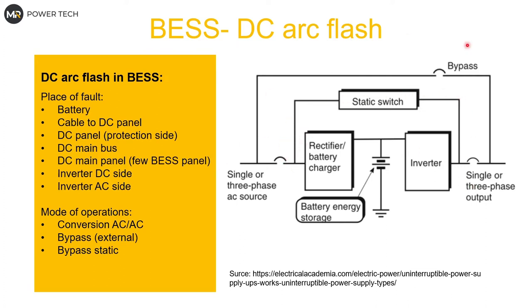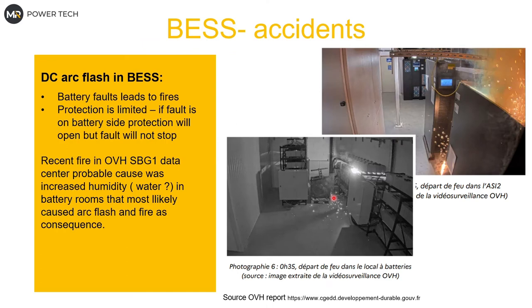Different modes of operation — bypass, double conversion, AC-to-AC — matter more for the AC side than DC. From what I found for real incidents: there was an accident at the OVH data center in Strasbourg, I believe in 2021. The official report — in French — stated it was a battery fault leading to fire, caused by increased humidity detected by sensors. For me, it looks like the battery fault created an arc flash which then caused the fire, and we know many websites went down because of it.